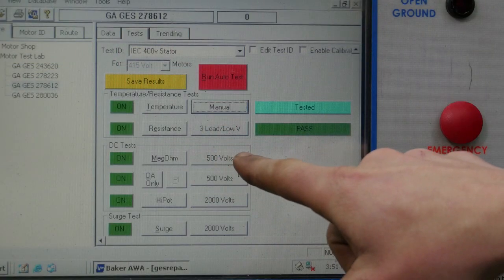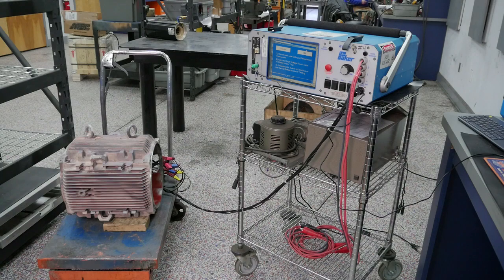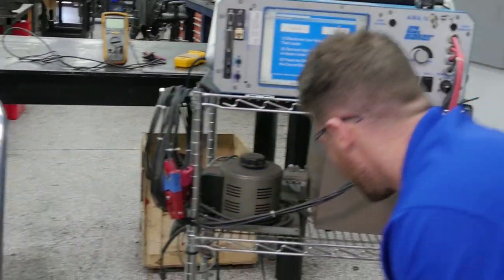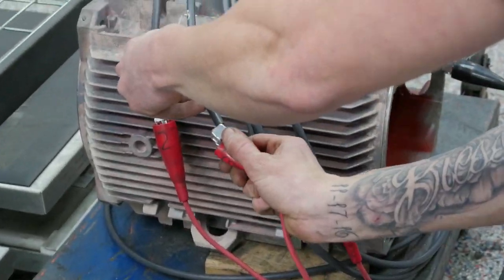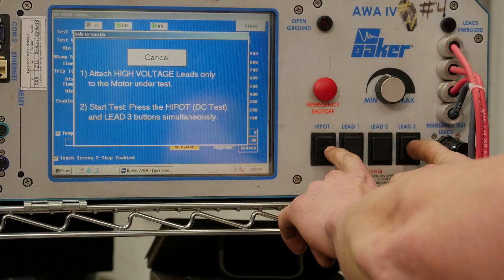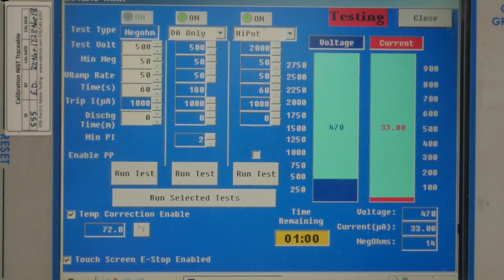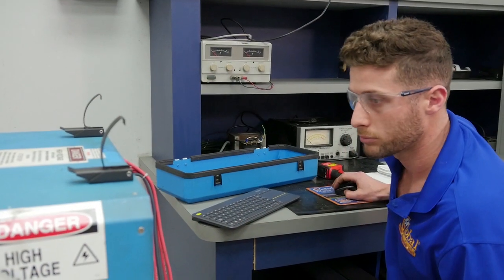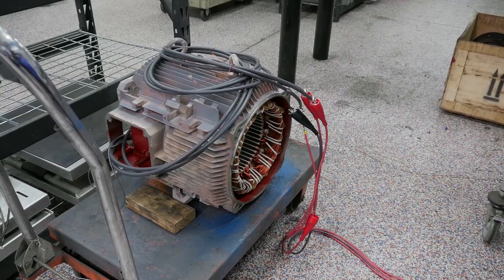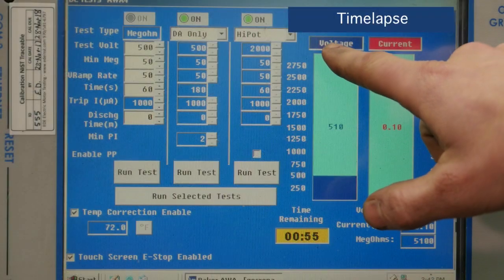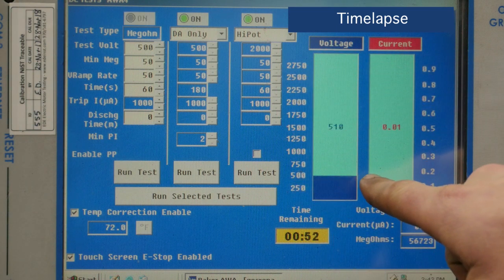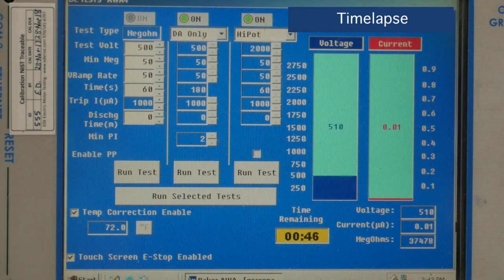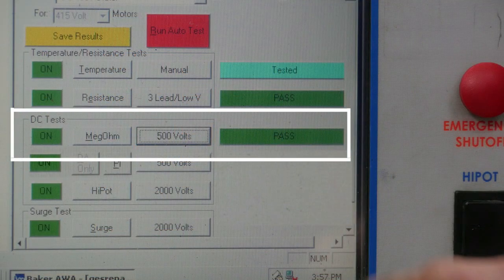Next, we move to our mega-ohm test. This test injects a test voltage similar to the motor's operating voltage. This voltage is held for 60 seconds, during which the analyzer watches for over-current conditions and abnormal insulation resistance readings, which would indicate a failure. If a low mega-ohm value is measured, we would inspect the motor for ground-wall insulation damage. Here, you can see the amount of voltage being applied during the test, as well as the amount of current the motor is drawing. This test has passed.